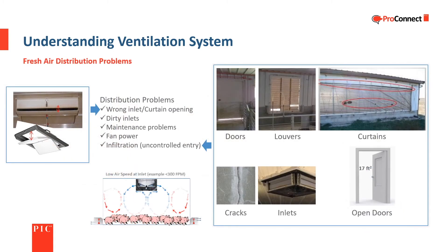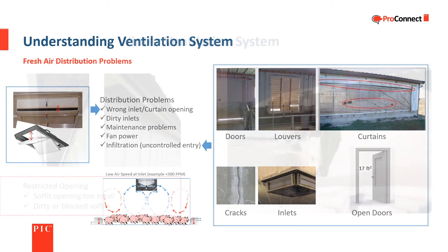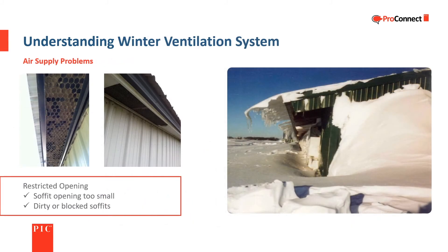For the system to work correctly, air needs to enter through the inlets at the correct speed. Fresh air distribution problems can be caused by wrong inlet or curtain opening, dirty inlets, maintenance problems, fan power, and infiltration, which is uncontrolled entry of air. Power ventilated barns need a plentiful supply of fresh air. A soffit or attic opening that is too small, dirty, or blocked will rob the system of air and result in poor ventilation.